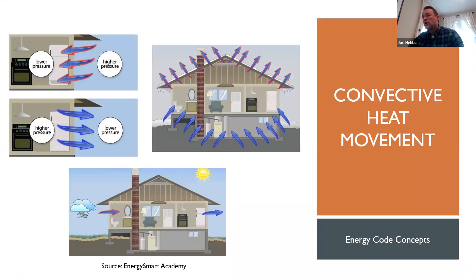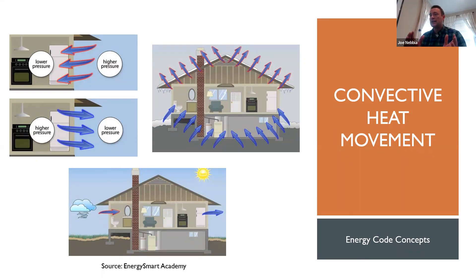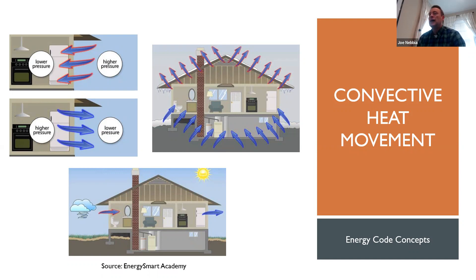With air sealing, a quick building science reminder: what we're trying to control is convective heat movement — heat moving with air movement. It's not conductive heat movement like we address with most insulation. Some insulation also stops convective heat movement if it's air impermeable. We're trying to stop heat loss because of air movement, whether it's heat loss from internal to external in the winter or heat gain in the summer. In a humid environment, we're also trying to stop moisture moving with that air. Air sealing doesn't solve all moisture movement problems, but it can help.